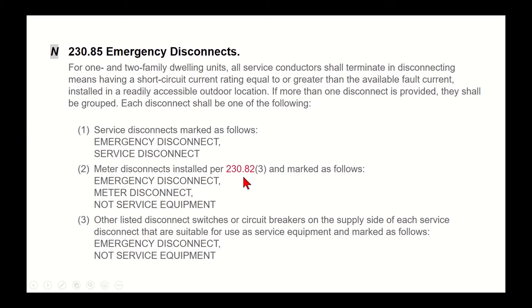Or if you want to put a meter disconnect — a disconnect on the supply side of the meter — then you have to mark it as the emergency disconnect, not a service disconnect, because then your service disconnect is after the meter.